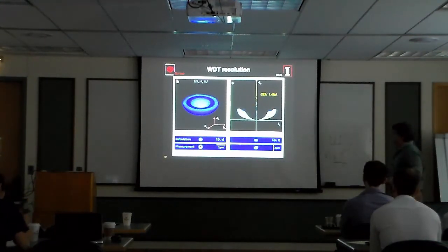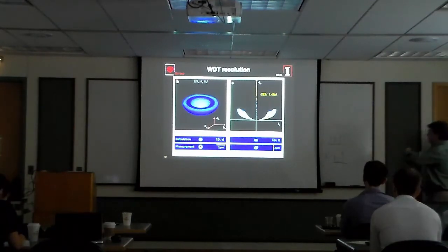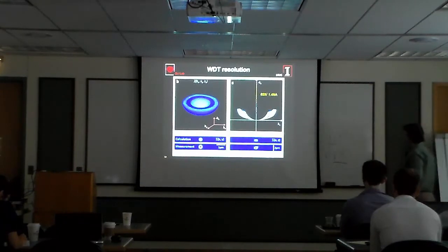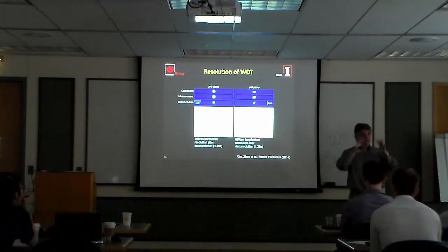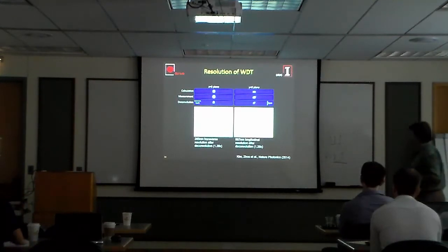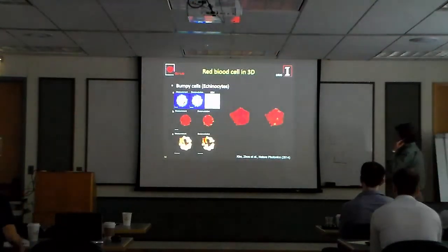So that makes sense. We measured small beads and compared our measurement with the calculation. So they match. You see here, they're close. They're not perfect, but it's pretty good. If you add some deconvolution, once you know this function, you can deconvolve your data with that calculation function. And you see that your PSF is going narrower, so you improve the resolution a little bit. Basically, in X and Y, we're at just below 300 nanometers. In Z, we're below a micron.